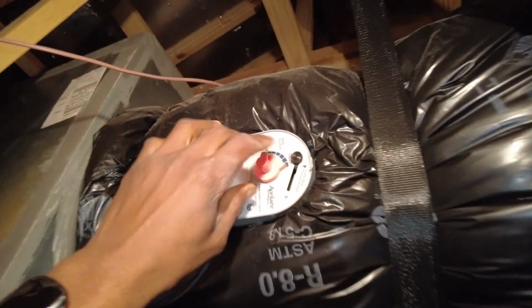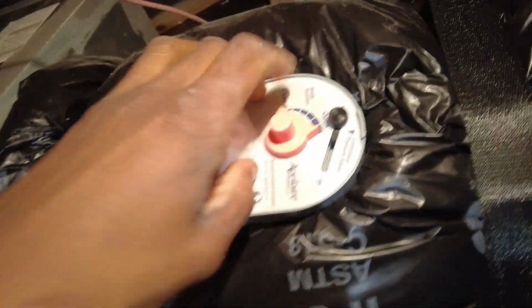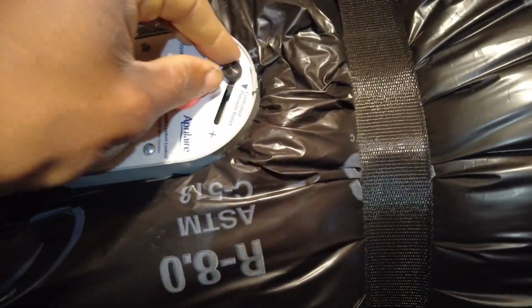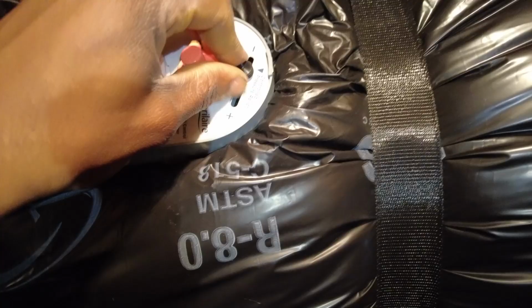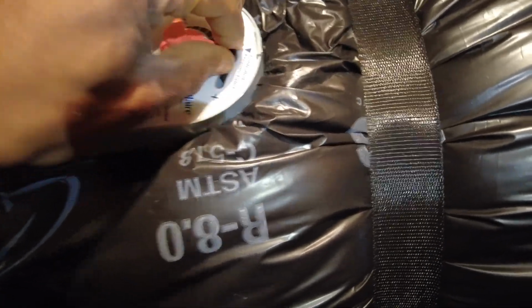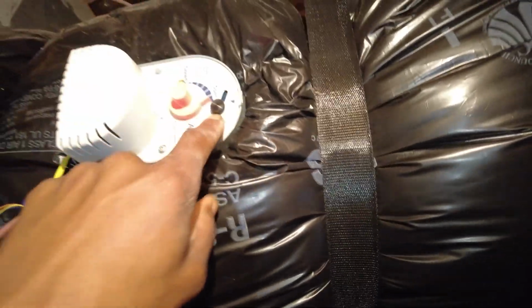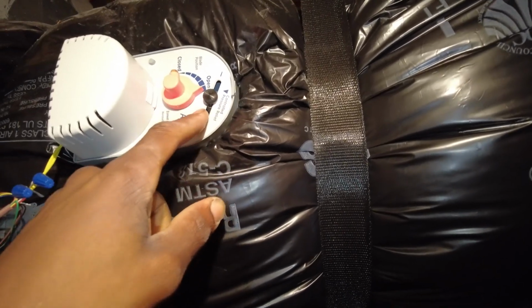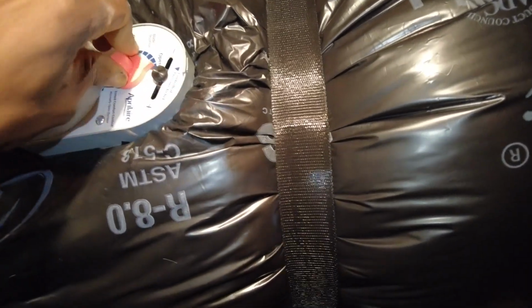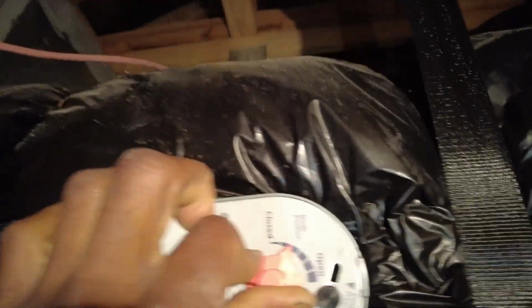Alright, and another thing we're going to go ahead and do as well, I'm going to set these pressure relief controls, and they're not necessarily pressure relief as much as it just doesn't allow it to close all the way. So I'm just going to set that to 50%. And that's not even 50%. The halfway mark isn't going to indicate whether it only closes. I mean, it's going to close about 60% of the way, as you can see. That's where it's stopping. So that's going to help as well.